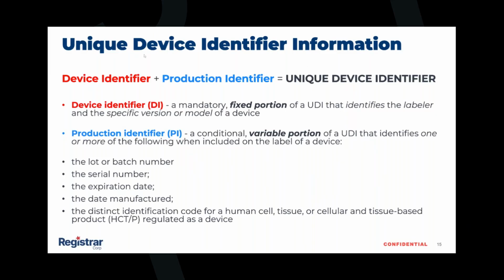Like I mentioned, your barcode is your DI and your PI part. It's in two parts. The device identifier is a mandatory, fixed portion of a UDI that identifies the labeler and a specific version or model of a device. The PI part is, again, the lot or batch number, serial number, expiration date, or manufacturing date.